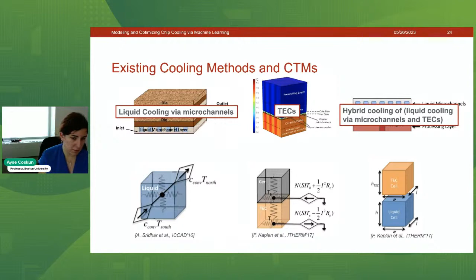However, based on the latest advances from our collaborators' lab, we wanted to model a two-phase vapor chamber. This is a passive cooling element, which is very attractive because one issue with liquid cooling solutions is that they need to connect to a pump to push water into the chip and collect it back to cool and feed it again, which consumes power. A two-phase vapor chamber is passive: the coolant absorbs heat from the chips and evaporizes into vapor, then the condenser condenses the coolant back into liquid and feeds it back into the evaporator. You can see a picture of this mechanism here.